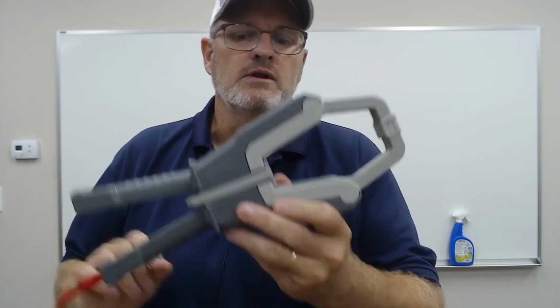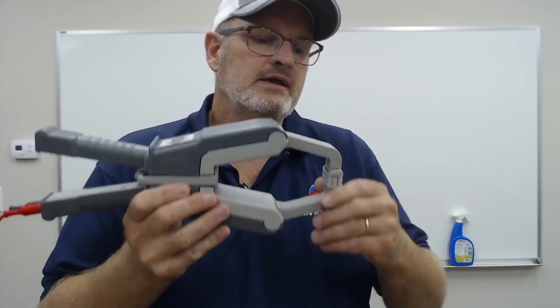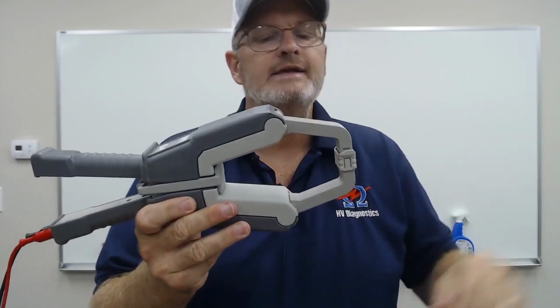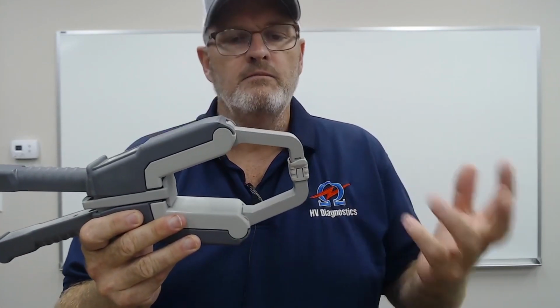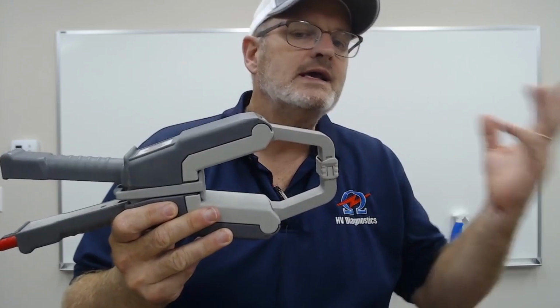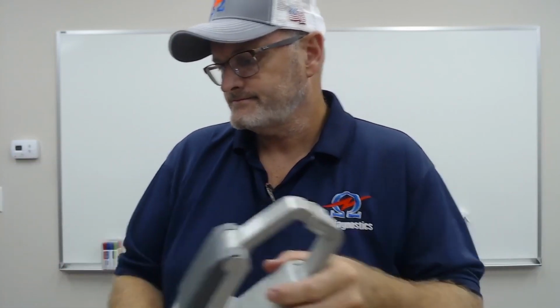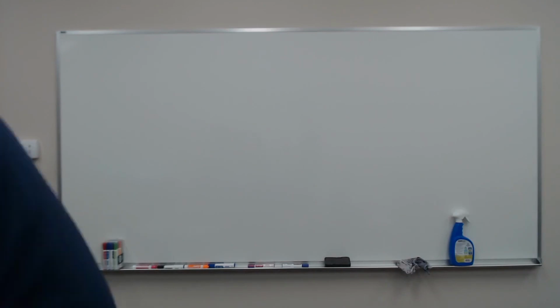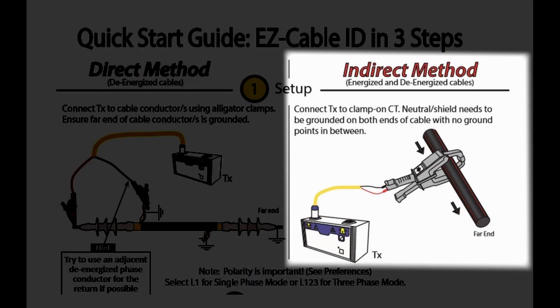This is called the indirect mode, because we are inducing into the cable, can be used on live cable. This method does have limitations. We'll talk about them later. Preferably, you always want to use the direct method on a de-energized cable. Yeah, just having a look at indirect method, you can see there the CT clamp connected around the cable in question. All right.